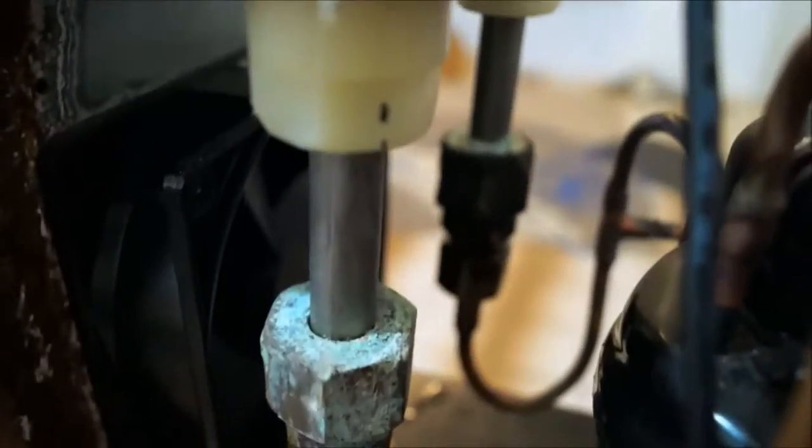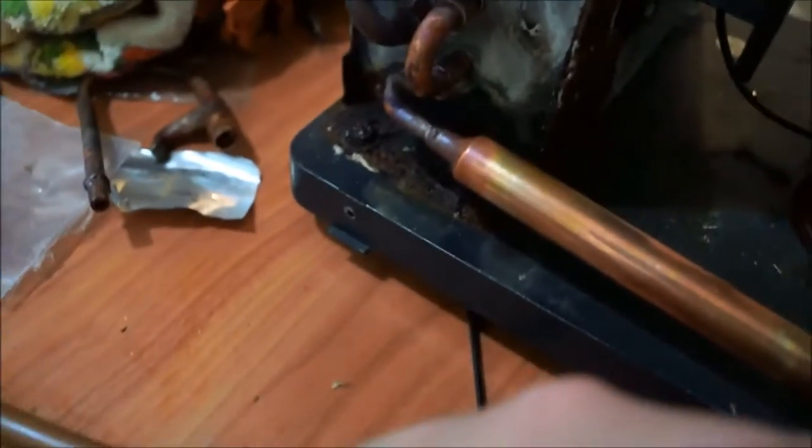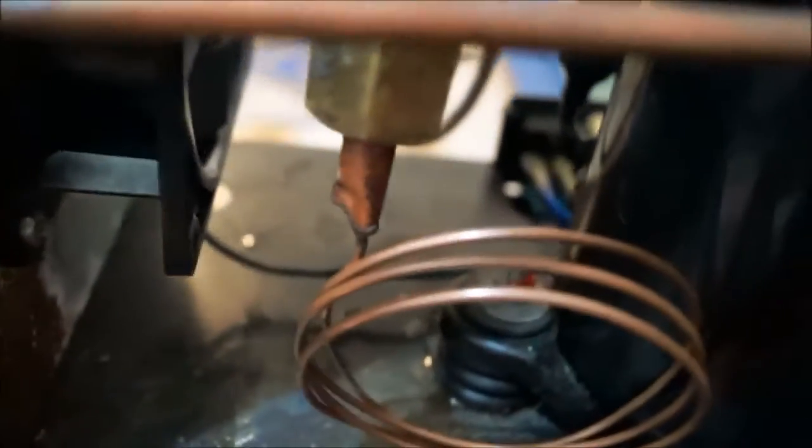These are actually flare fittings because this is aluminum tube for corrosion. As you can see I think this has had a leak and it's probably been used on a saltwater tank, so it's a bit nasty. I put the new capillary in, just crimped a bit of tube and brazed it on in there.